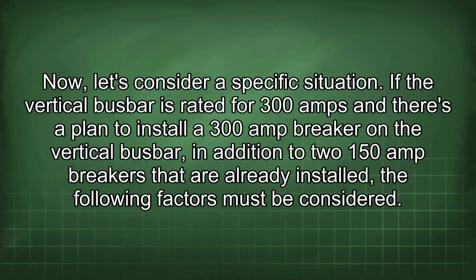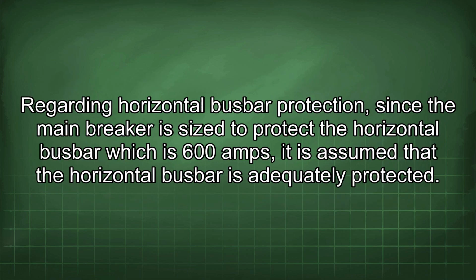Now let's consider a specific situation. If the vertical busbar is rated for 300 amps and there's a plan to install a 300 amp breaker on the vertical busbar, in addition to two 150 amp breakers that are already installed, the following factors must be considered. Regarding horizontal busbar protection, since the main breaker is sized to protect the horizontal busbar, which is 600 amps, it is assumed that the horizontal busbar is adequately protected.